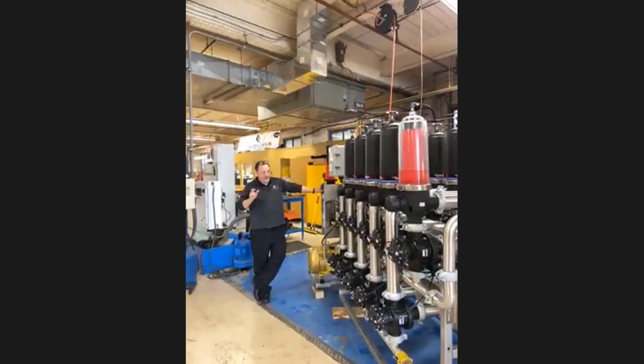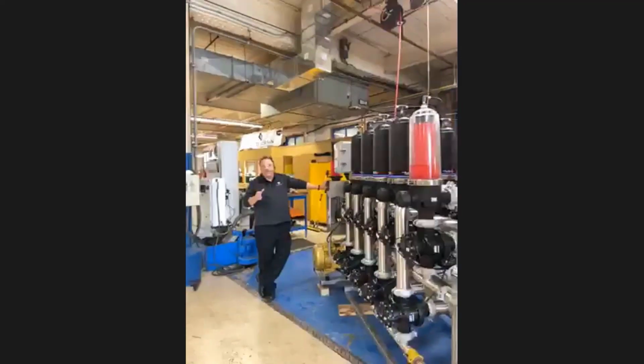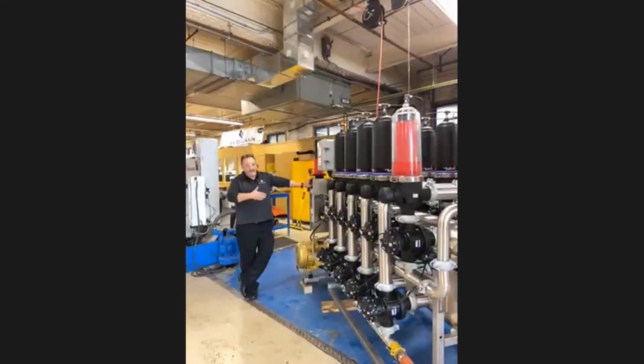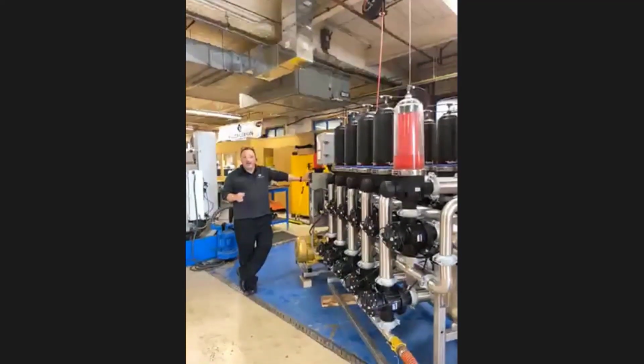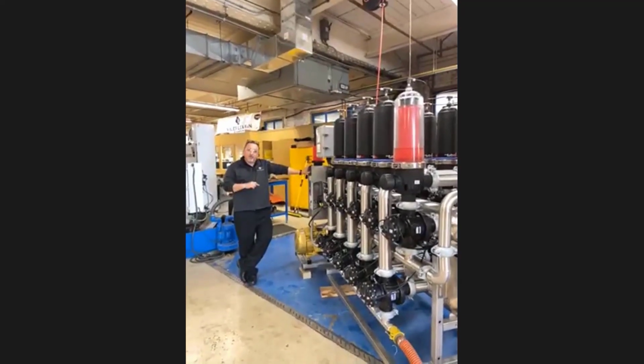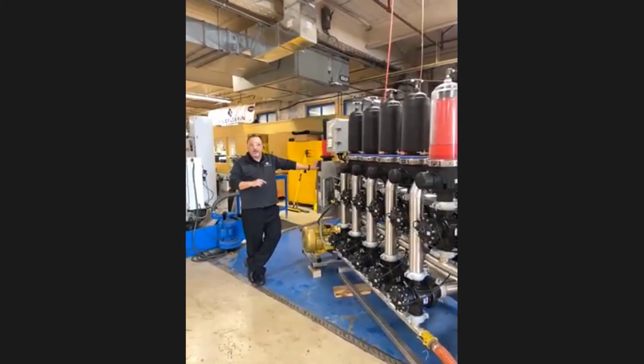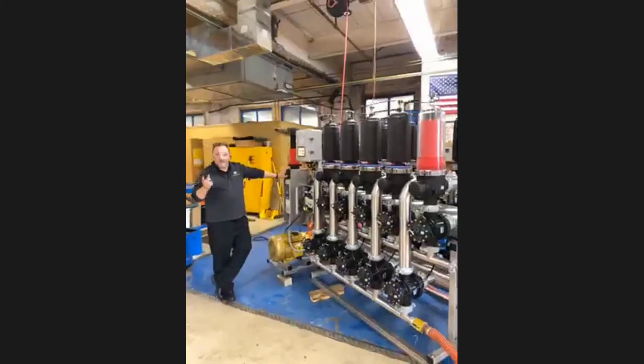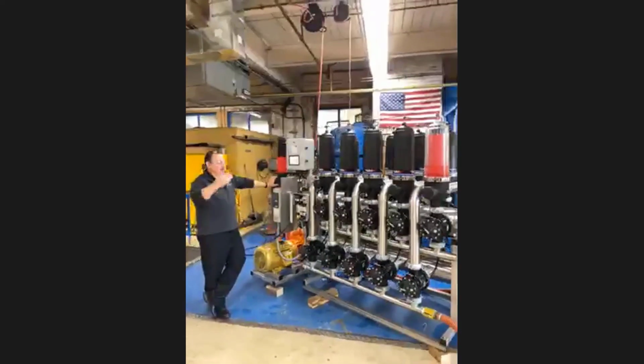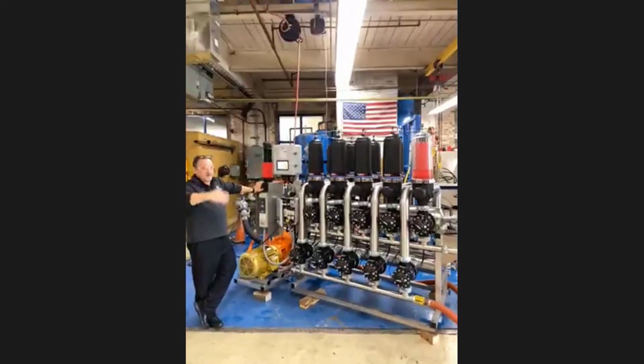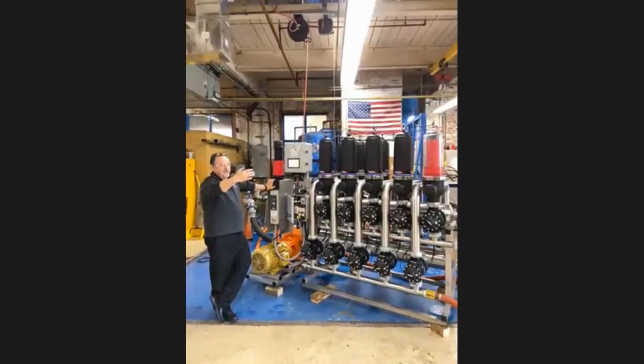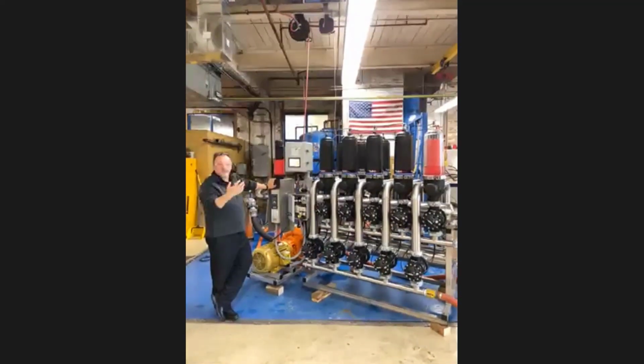Thank you for repeating it. That's a great area where a VFD comes in, where say you have this 10 pod, but now you only want to run it at 600 GPM. You could have a VFD and you're probably only running then, probably 35 Hertz. And then as another tower goes in, you might be up to 44 Hertz or whatever. And then when it's built out to 1,000, you might be running then at the 60 Hertz.